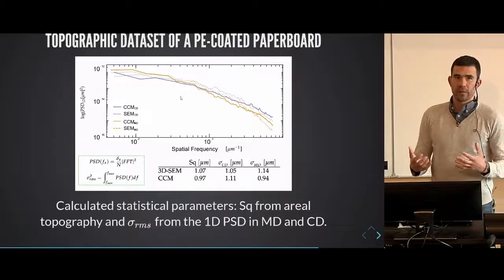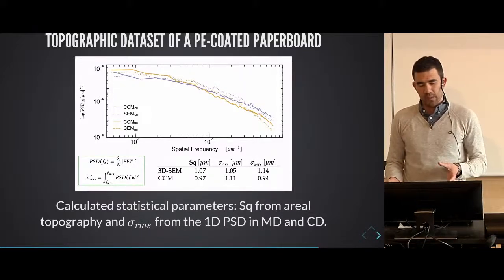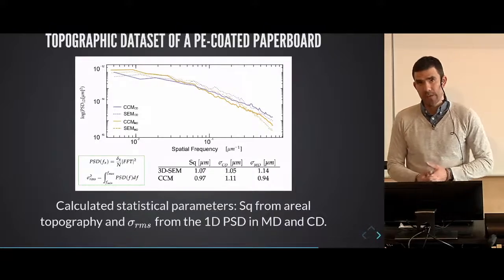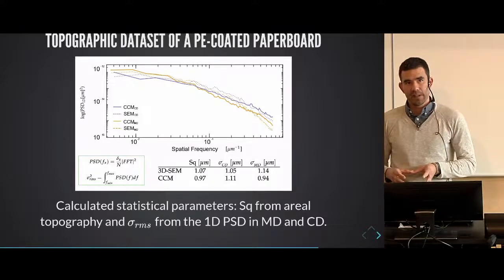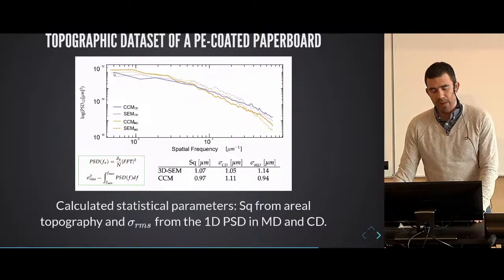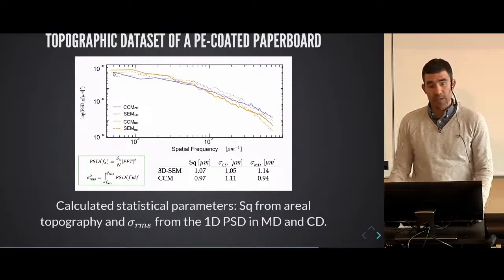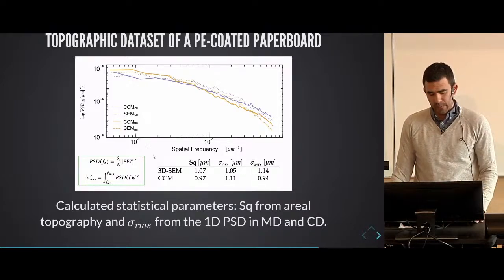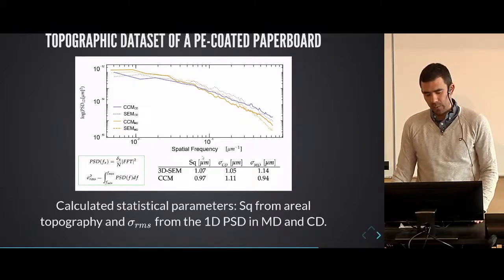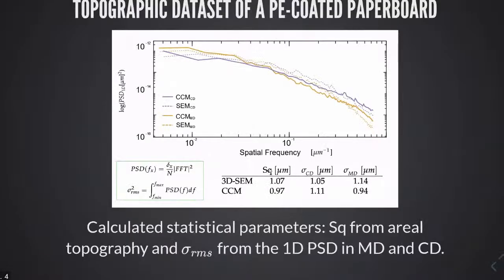For a more honest way of comparing instruments, we use the spectral information of both instruments, accounting for resolution and the step size of the scanning, and we match them. So both techniques can measure in a similar way. What we measure is the power spectral density function — essentially the spectral representation of surface roughness. We also compare a statistical quantity from the new ISO standard: the areal root mean square of the surface roughness. This also shows good agreement between the two instruments.